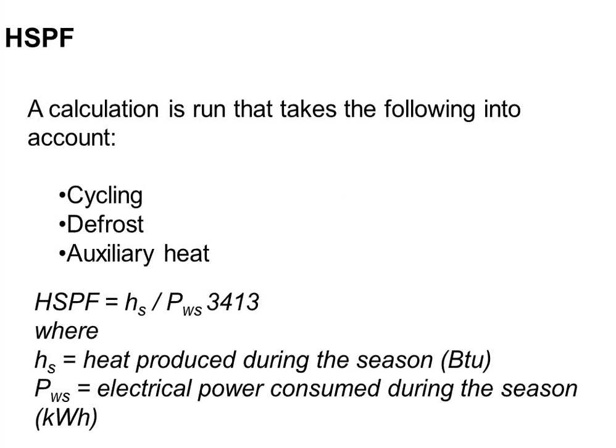That's the old school way of doing it, that they did it in heat pumps forever and ever. With newer units, with the smarter controls, we have the sensors on there to look at the outside air temperature and to look at the saturated condensing temperature. And then we can calculate if it's actually going to be a frost scenario at that moment in time or not, and only enable the defrost cycle when I'm actually going to witness frost on the unit.